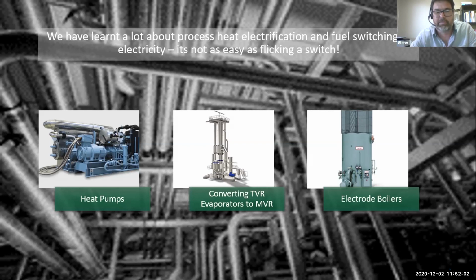Unfortunately, we found similar issues with converting from TVR to MVR. What we found was that the thermal vapor recompression unit is quite a small thing, and the mechanical vapor recompression unit is actually quite a big thing, so we couldn't physically fit it inside the building. That meant, in effect, a 2-story building that has to be big enough to carry the weight of quite a heavy piece of equipment, and also be clad and accessible for maintenance and operation. So again, what we found was that the total capital cost of installing a TVR to MVR conversion was on the order of 2 times larger than what we first imagined.